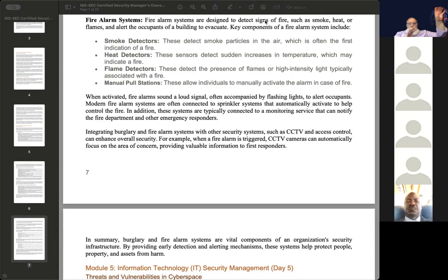if you have air that blows somehow, it will not work because the smoke goes all to the ceiling. Okay? But if you have these systems, wherever you install it, at the ceiling or lower, when the smoke comes, it will give you alarm, you know, because it will pass to go up. And with 3 or 4 of these beams, you can cover an area of, I don't know, 1,000 square meters, maybe more, 2,000 or 3,000 square meters, big warehouses. In warehouses, you are not able to put ionizing smoke detectors because of dust.